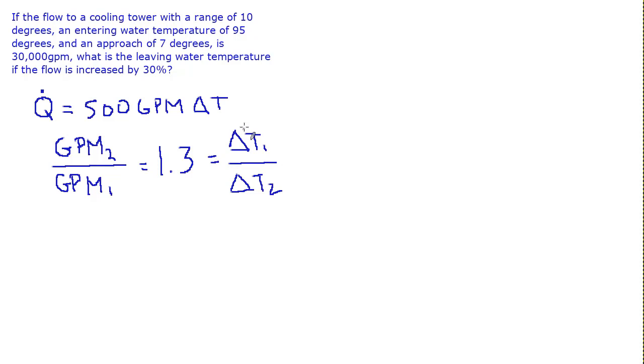We know delta T1 is the water delta T in the cooling tower, which is the same thing as the range. This is the condenser water return minus the condenser water supply, or in this problem, the entering water temperature minus the leaving water temperature. So that was originally 10. We can plug that in and solve for delta T2. Delta T2 turns out to be 7.7.